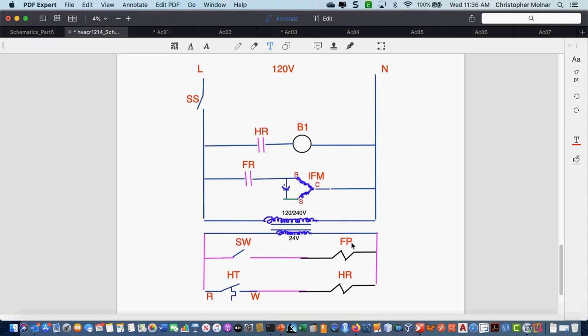Okay, so I'm going to change that name to fan relay. What is the sequence of operation? Anybody? What is my sequence of service operation? Switch closes, transformer is powered, then your SW switch is powered, powering your FR. FR then powers the run winding. Your heating thermostat calls, which powers your heating relay, which powers bulb 1. Yep.